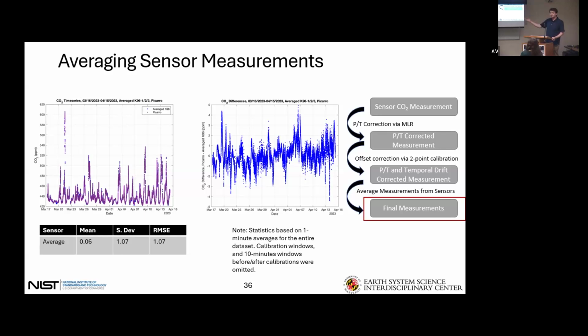Now, this changes based on the sensors. I've seen sensor pairings where we've been able to get them down to 0.97 ppm for RMSE. So it really depends on each of the sensors. Each sensor performs a little bit differently, which is why each one needs its own correction coefficients. But in the end, we're able to get a highly accurate measurement from sensors that are only $500 a piece.